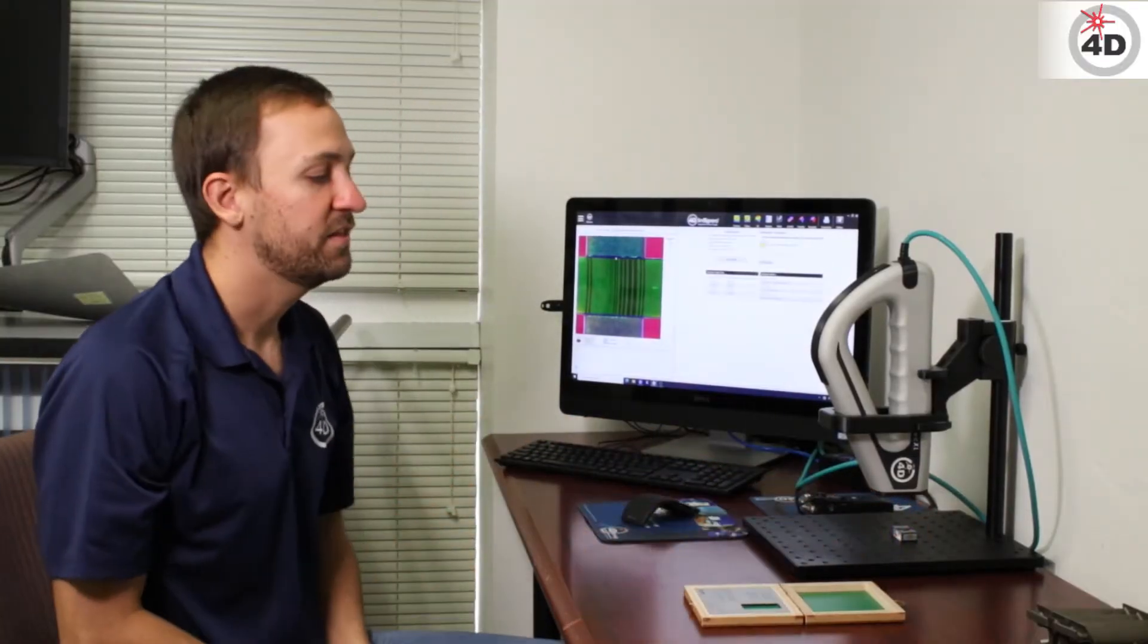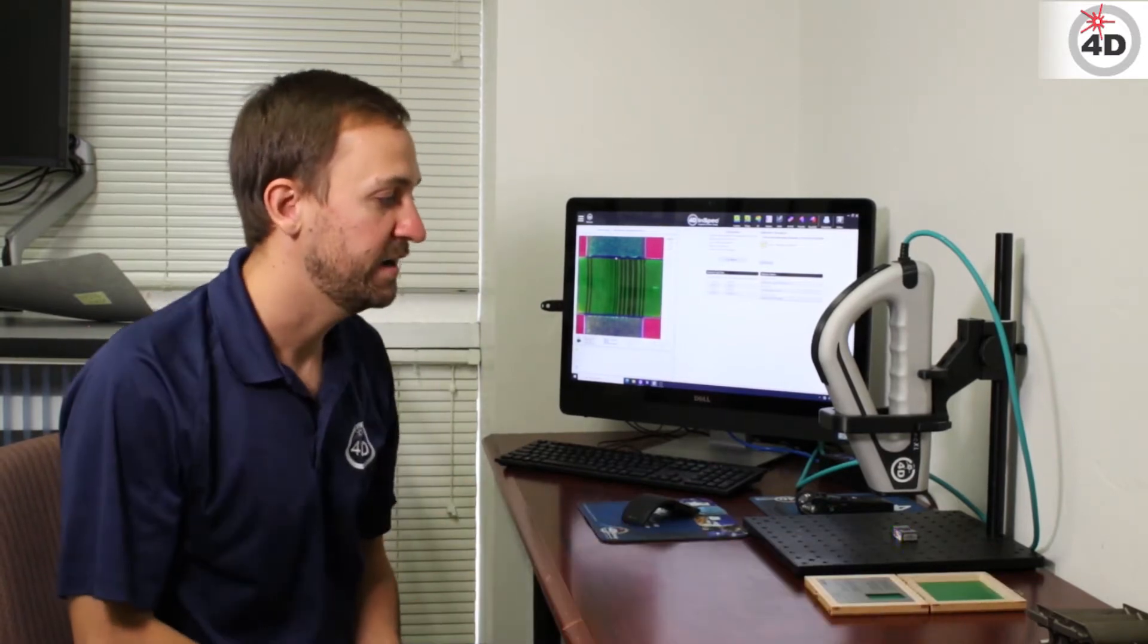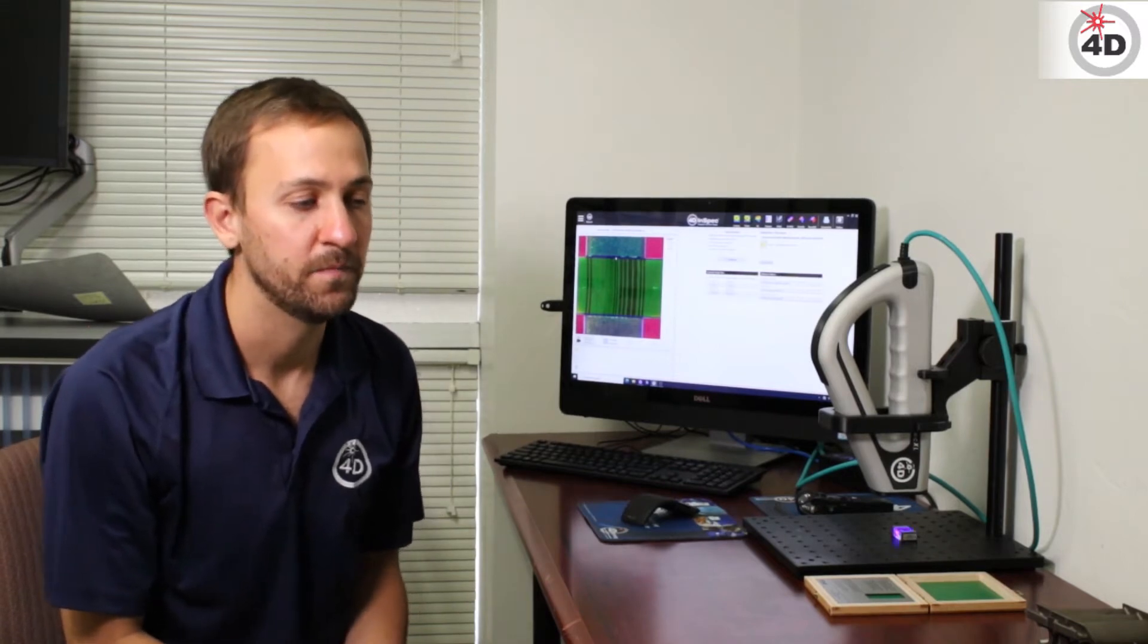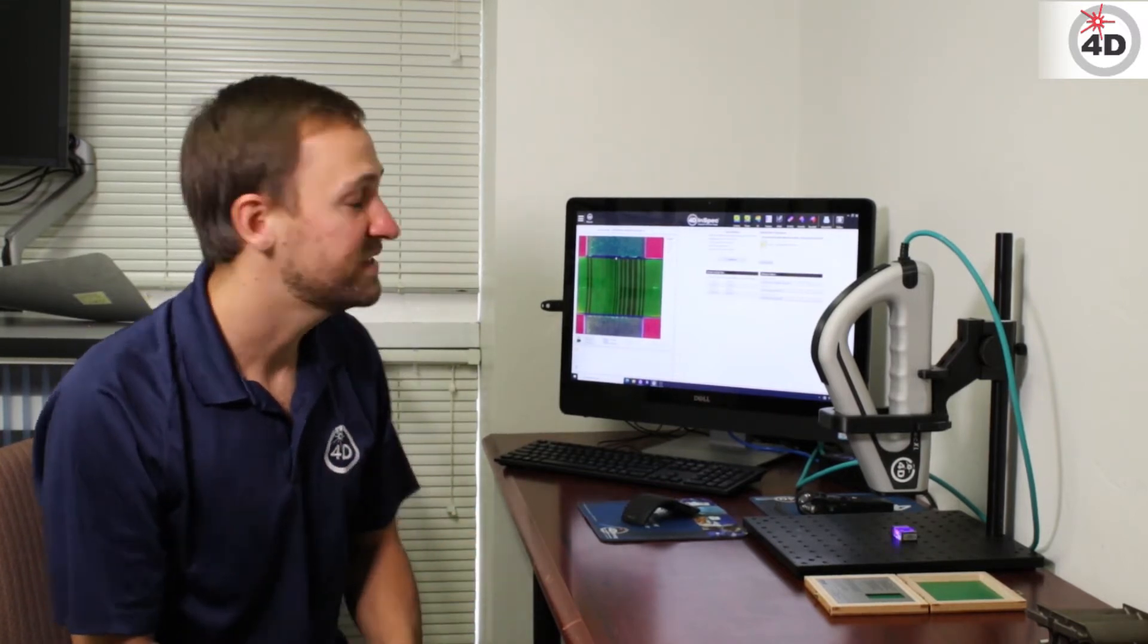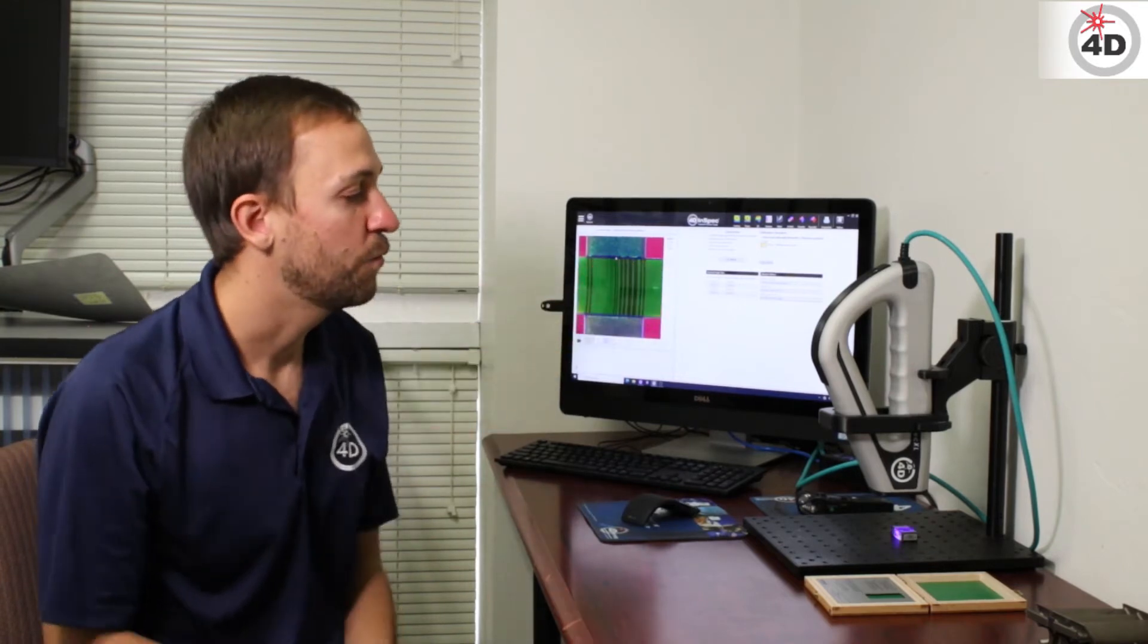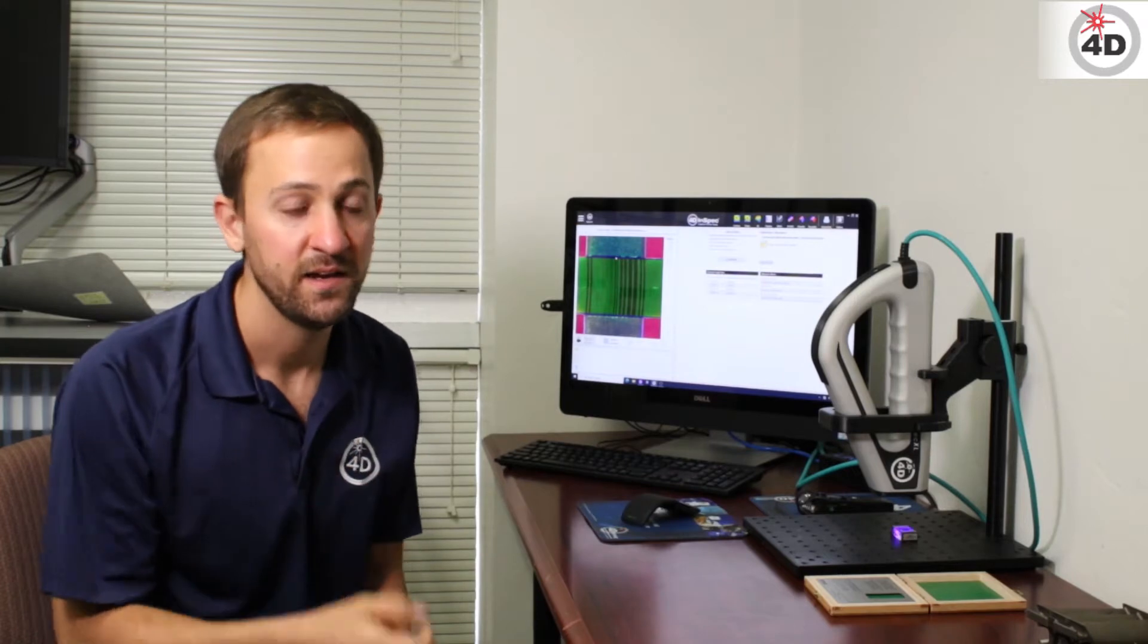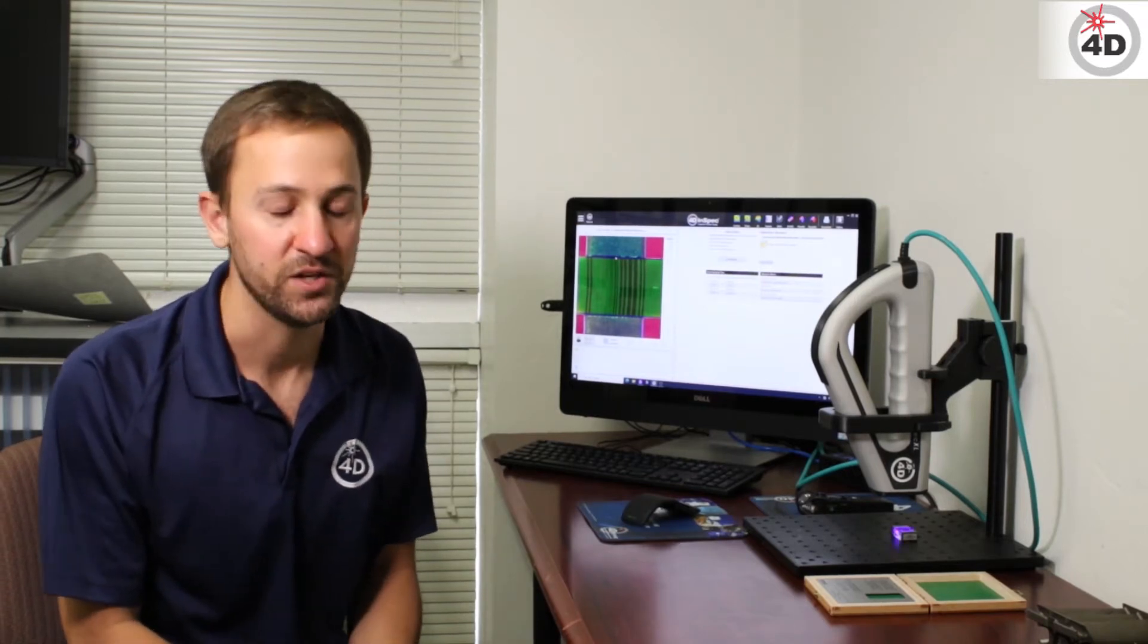And the tricky part with this calibration is that the XL has a bigger depth of field. So with the smaller standard size, if you're not in best focus, it's really obvious. The colors go green, you can tell you're out of focus. Whereas with the InSpec XL, the depth of field is over three times as big. So you actually get green over a nine millimeter range.